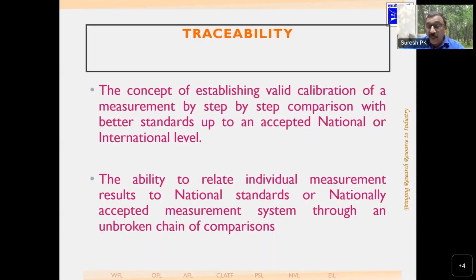So they have a comparison level. At RRSLs, they have comparison standards, which are calibrated against the national standards, and they try to transfer the standards to the industry through their regional reference standard laboratories. So when they say that you have to calibrate once in a year, there may be so many reasons by which your calibration may shift. But you have to ensure that it is within limits, or within the accepted norms.